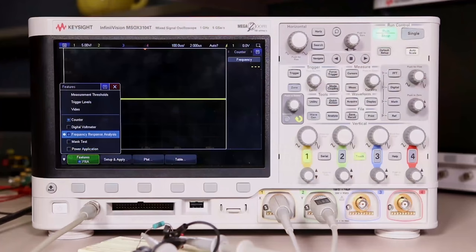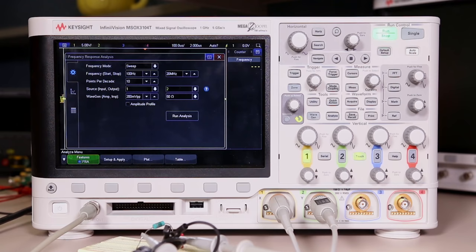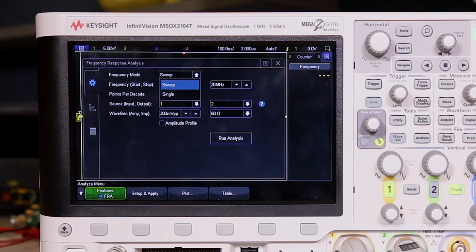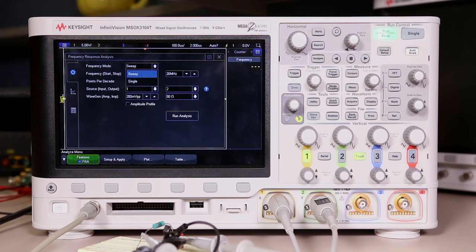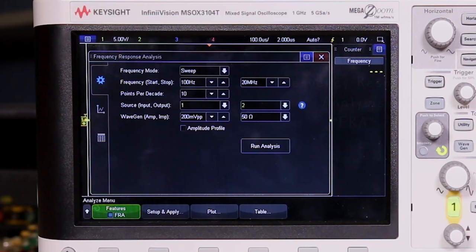And we can see the first menu is the setup and apply menu. This is where you can configure the settings for the specific tests that you're working on. You can set up a frequency sweep which is most typical but you can also change the frequency mode to single just to test at a specific frequency. And this is helpful when you know there's a problem area in your device. You can also adjust the start and stop frequencies that the wave gen will sweep between along with the source and the amplitude of the signals.